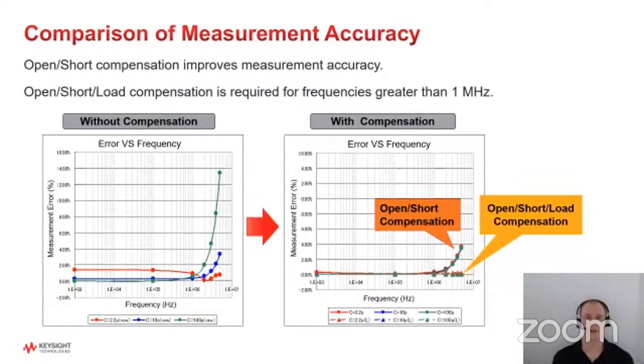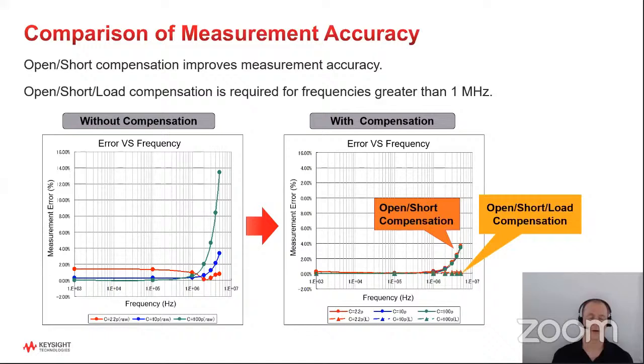So this slide shows a couple different things. On the left, you can see measurement error done on some different devices with actually no compensation at all. So you can see that you do get quite a bit of measurement error right away if you don't have any compensation. So as I said, you have to do at least minimum open short compensation.